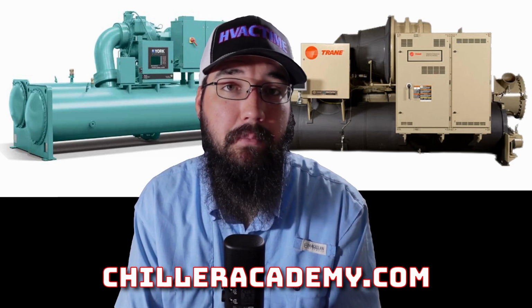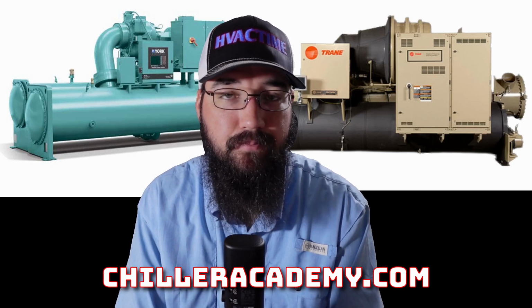By low pressure, let's give some examples. Some high pressures: 134A, 513, that's the new one coming out that's going to be replacing 134, 410A and R22. These were high pressure refrigerants, all of them. And basically, the short story is they operate above a vacuum. So they do not go below 0 PSI for their normal operating conditions. They stay above that. That's just very rudimentary. This is what we qualify as a high pressure machine.